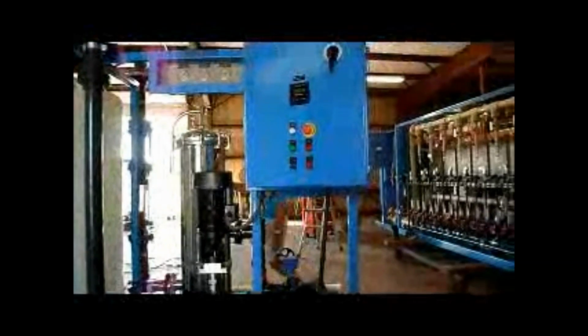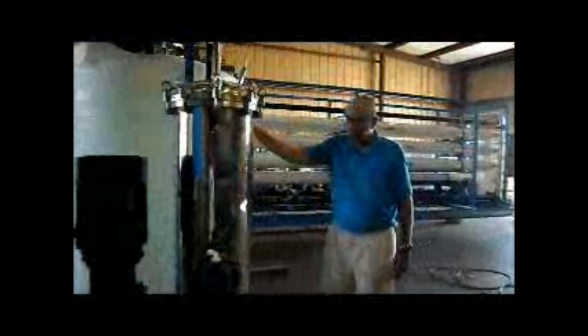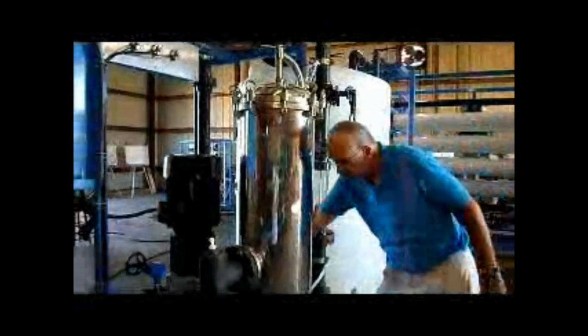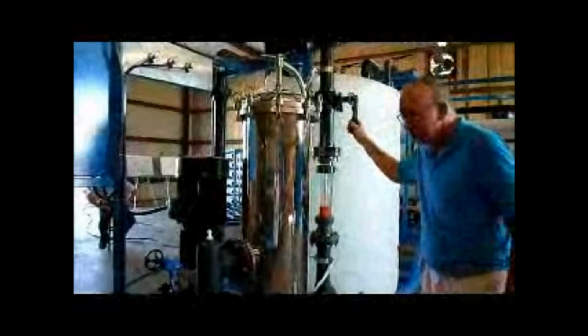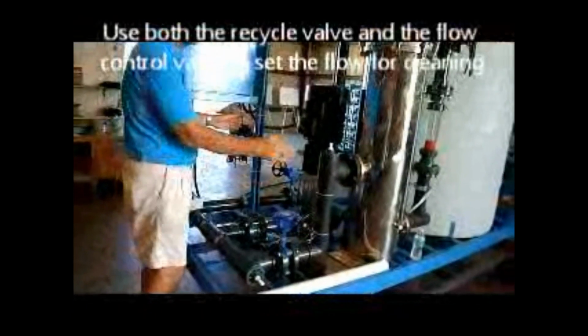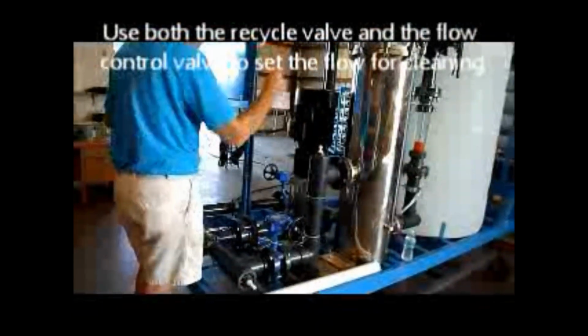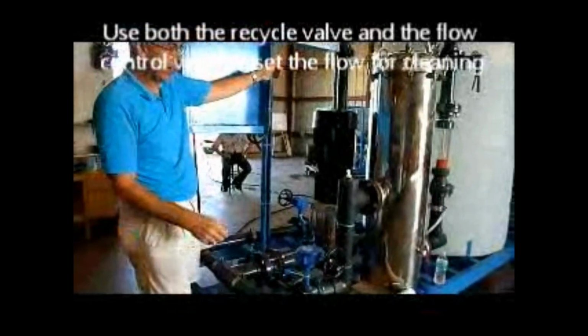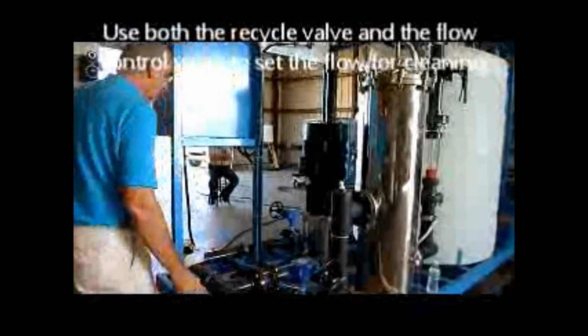Last valve, this is the cleaning solution out. So under normal operation, this valve will be open, this valve will be open, and then you use these 2 valves to adjust the flows. How much water or solution goes out to the skid, how much solution recycles back into the tank. Adjust those 2 valves back and forth.